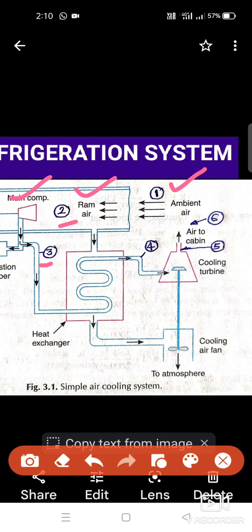In the compression process the temperature and pressure of the air is increased, and now from 3 to 4 there is a heat exchanger. In the heat exchanger, at point number 3 high temperature, high pressure air is coming into exchanger, and at point number 4 we get the cold air, and that cold air is expanded in the cooling turbine. This is the expansion device.